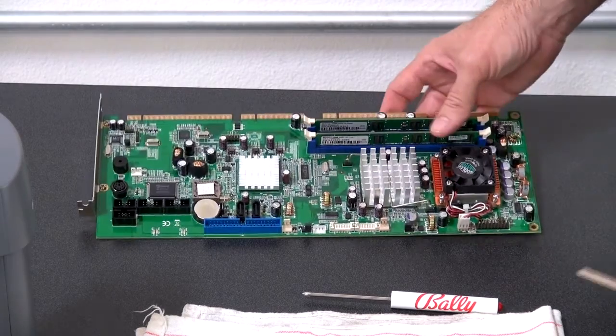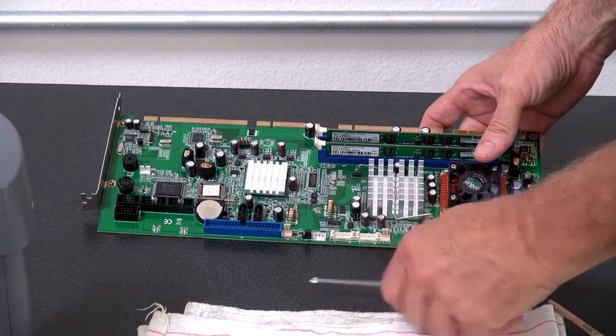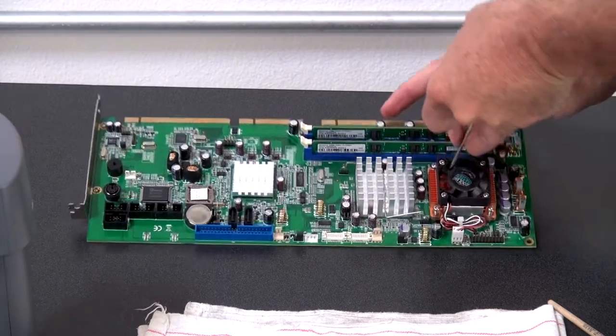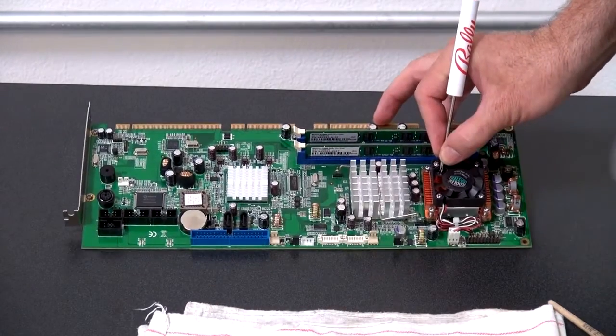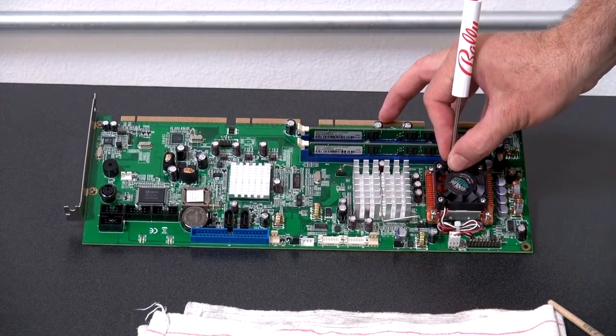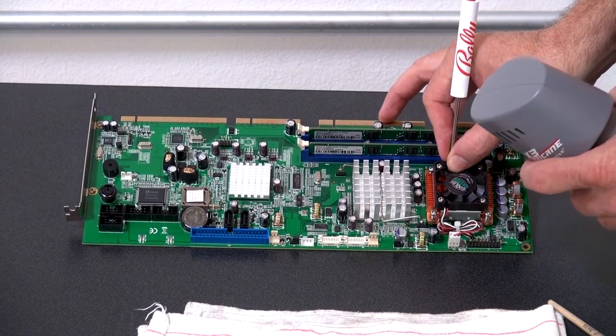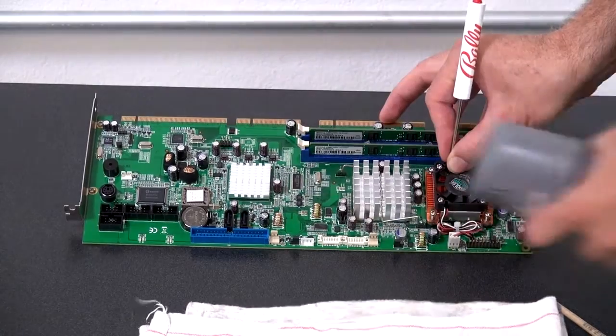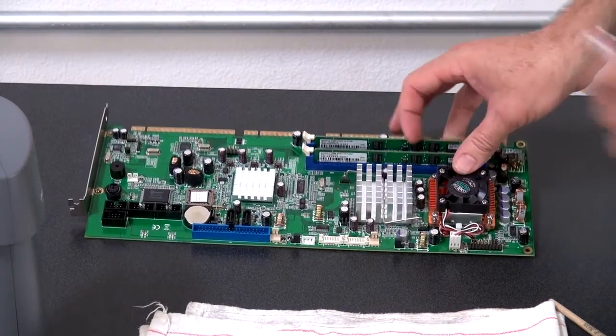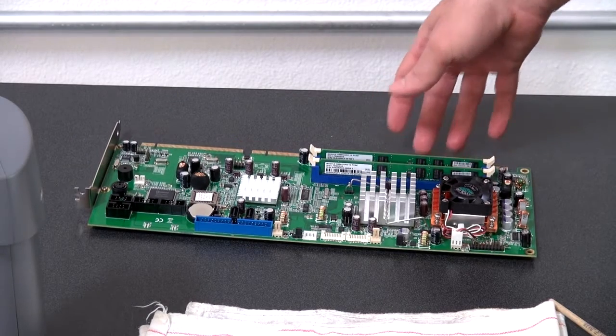When cleaning the main MPU board, first you want to blow off all dust and debris. Insert something into the fan to keep the fan from spinning as you blow it. This will ensure that the blades don't spin backwards and risk burning out the bearings.